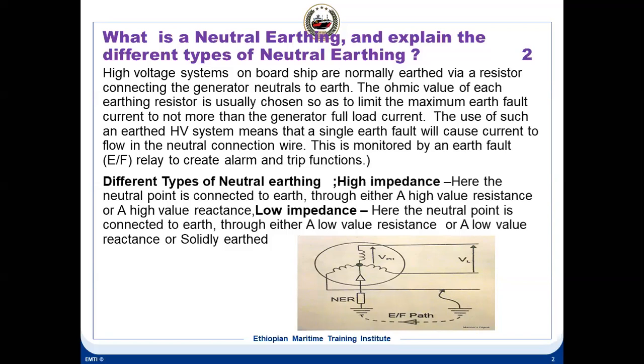High voltage systems on board ships are normally earthed via a resistor connecting the generator neutral to earth. The ohmic value of the resistor is usually chosen to limit the maximum earth fault current to not more than the generator full load current. And this is monitored by an earth fault relay to create an alarm and trips. So there is also a CT on this same line, on the NER line, which can sense any excessive current flowing and give an alarm and also trip functions.